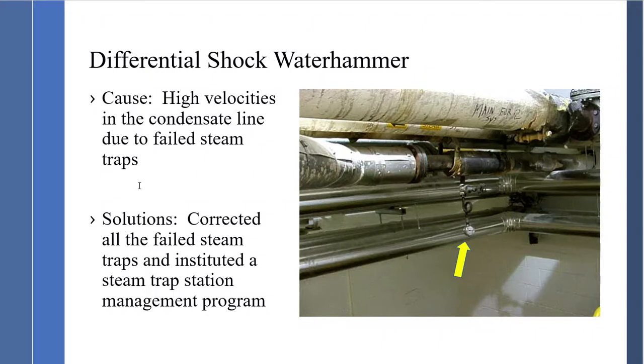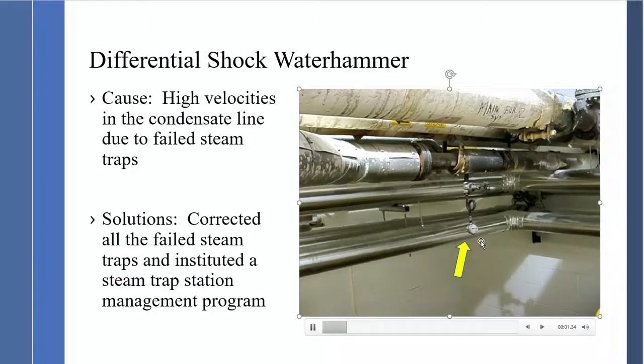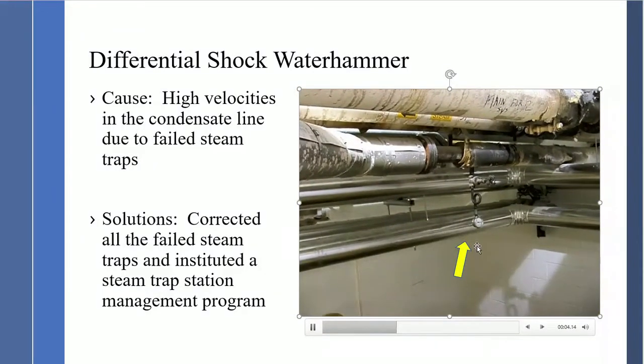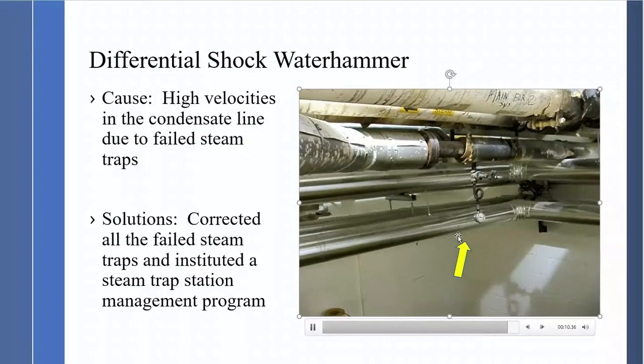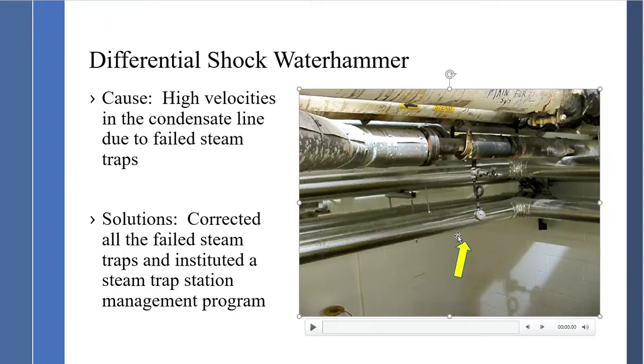An example of high velocities in a condensate line: watch the pressure gauge — you can see it spike when the wave comes down the condensate line. The pipe supports were damaged and near failure, with flange failures and weld failures occurring. The correction was implementing a proper steam trap management program, as so many steam traps had failed and were blowing steam through, causing the high velocity in the condensate line.